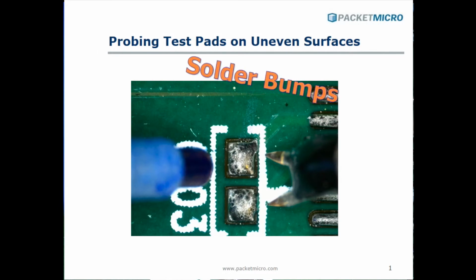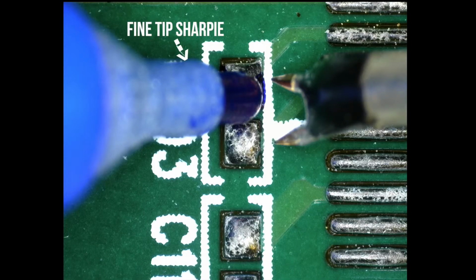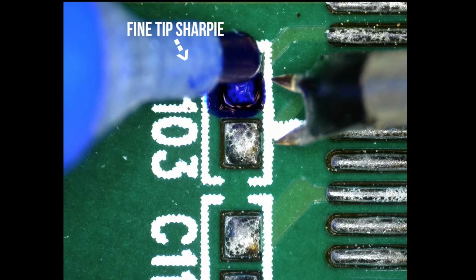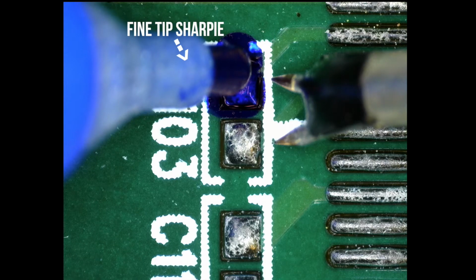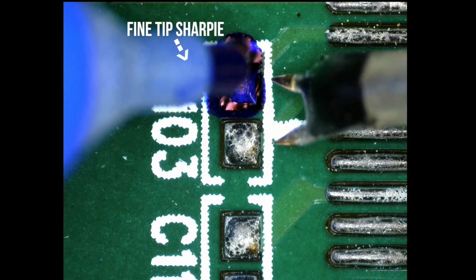Sometimes you may need to probe on solder bumps that are typically on uneven surfaces. In this case, the Mylar approach no longer works, so we need to go back to the conventional way of observing the probe tip skid marks. Since it is difficult to see the skid marks on the solder bumps, color the bumps with a fine tip Sharpie to make the skid marks more visible.